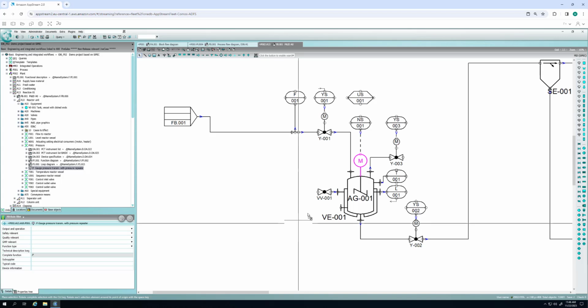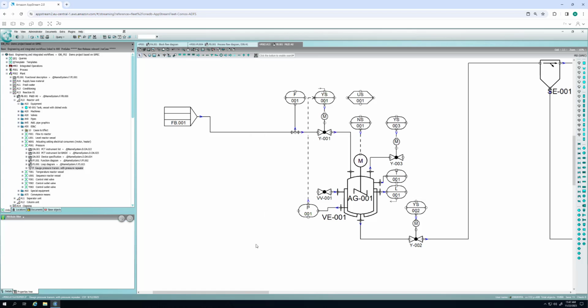Another role is electrification of all the consumers, where you can specify that the agitator drive needs to have a power of 8 kW, so that you can do a good dimensioning of the switchboard, and instruments can be added to stabilize the process inside of this reactor vessel, just connecting it and interlocking, for example, this valve here.